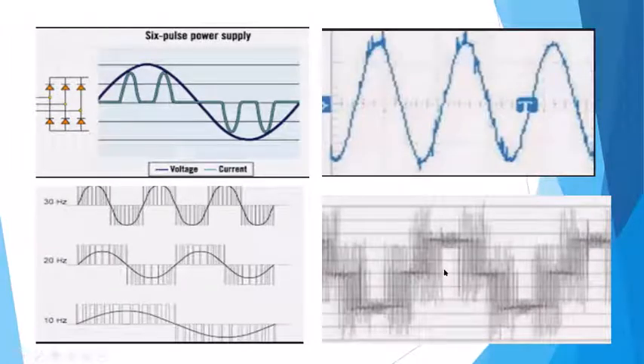And then you also have to be aware of another big factor in motor failure, this PWM. My rule of thumb is, if a motor is over 100 feet away from the output of a VFD, you really need to be cautious of what happens, because as the two wires are alongside each other, they create a capacitance effect between them, and they end up creating these higher spikes. So the voltage peak to peak can jump up as high as 1,600, 1,700, 1,800 volts peak to peak. Well, the original insulation in a lot of motors was much lower than that.